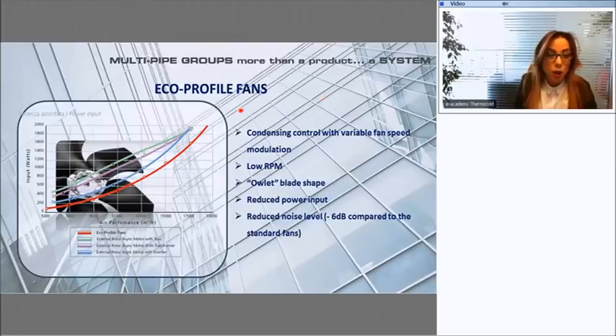the frame is much more light, and it ensures very easy maintenance operations. The unit is also equipped with the electronic expansion valve, and the electrical panel includes the Modbus card as a standard feature, automatic changeover for the hydraulic version, so it means that if you select double pump version, the changeover between the two pumps is made automatically and not manually. And another standard feature of the unit is the phase failure relay.